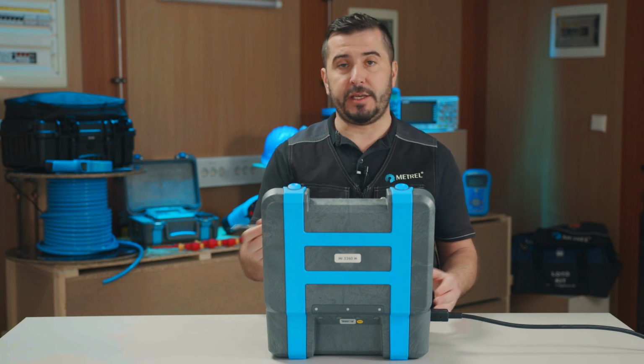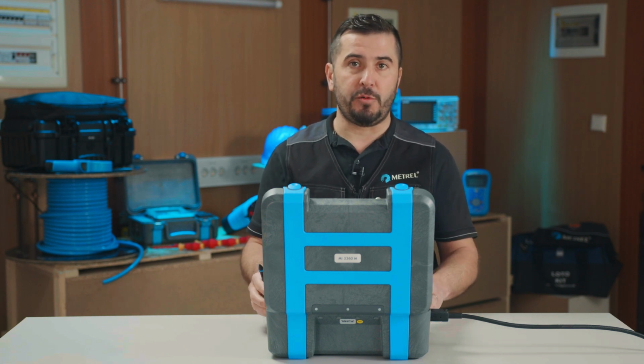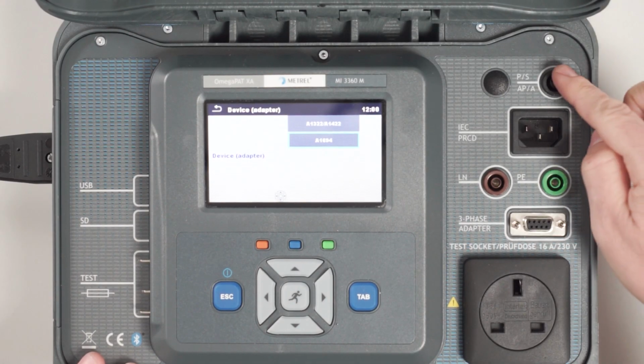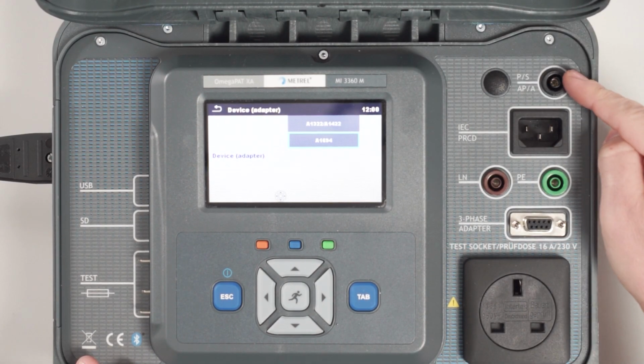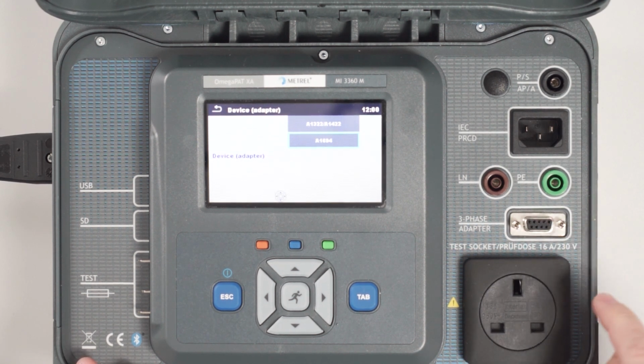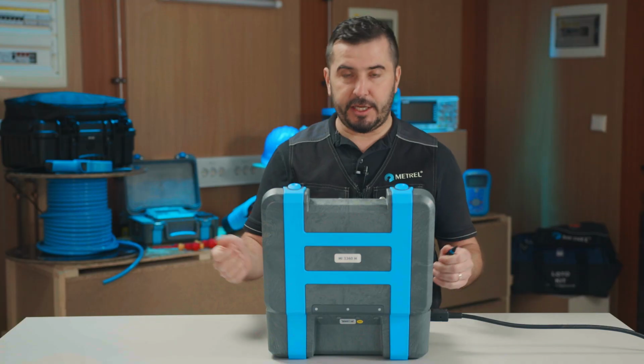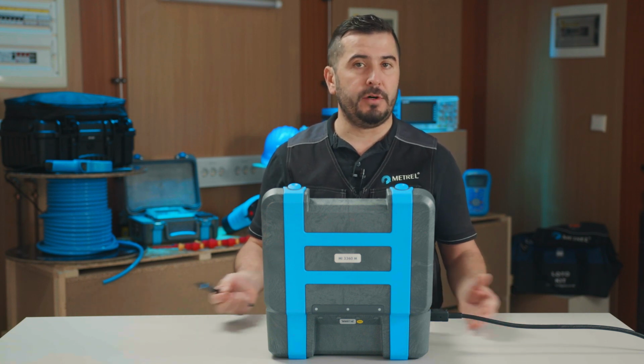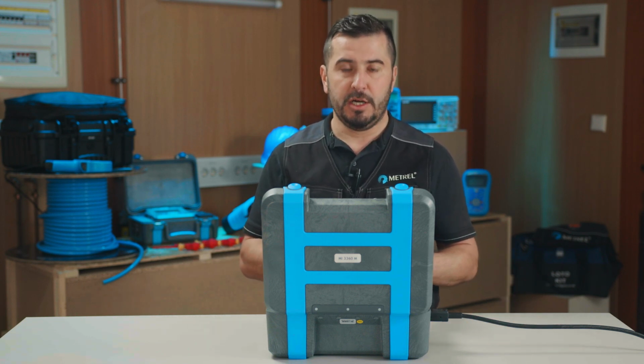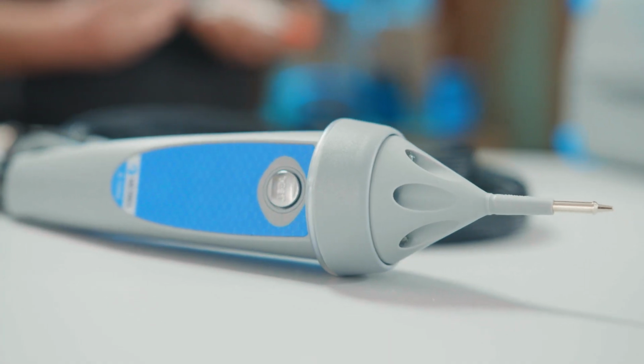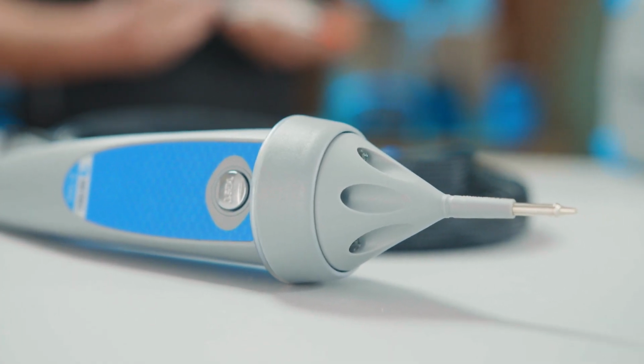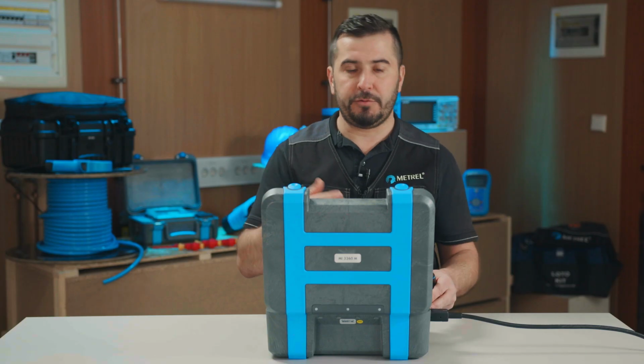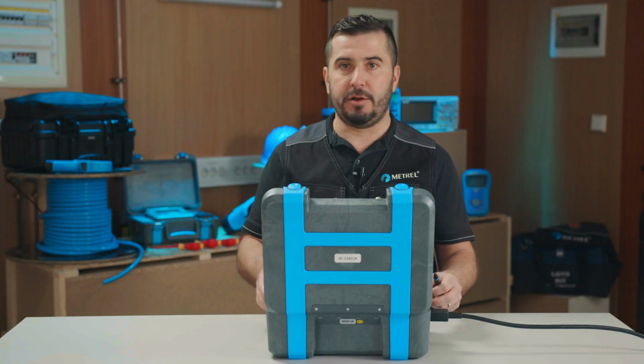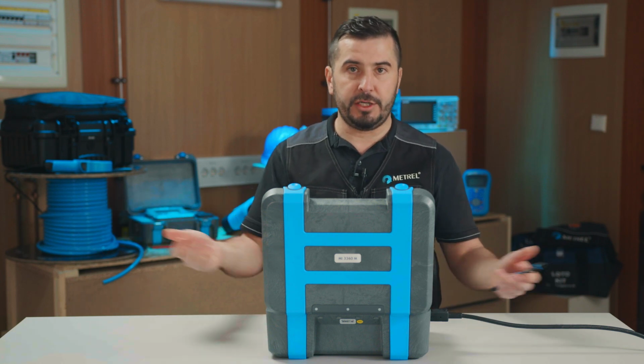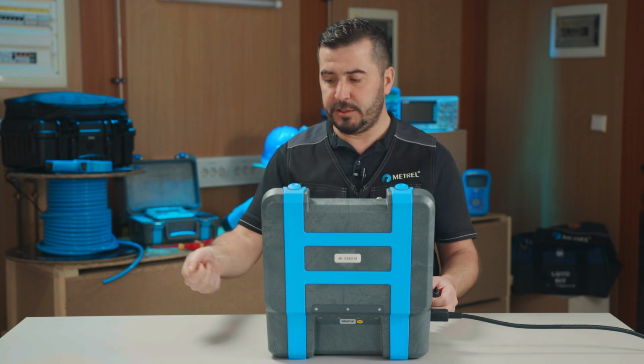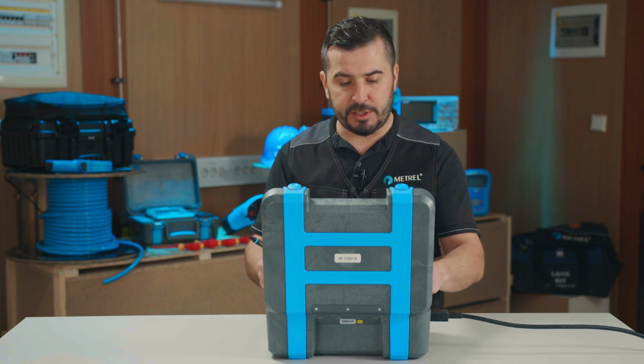Or we can connect A1694, and this is actually a remote tip commander, which is connected between this PS port and this 9-pin serial port, and it can be used for measuring of earth continuity or other measurements where the probe is needed. What is good about this commander is that it has actually a start key on it, so if we have to go under the table, for example, or we have many locations where we have to perform the measurements, we can simply perform it by remote start on the commander.